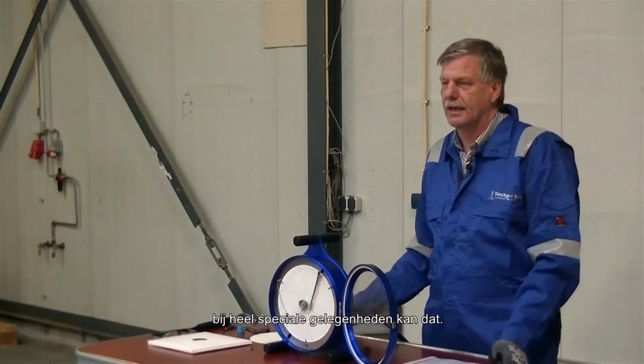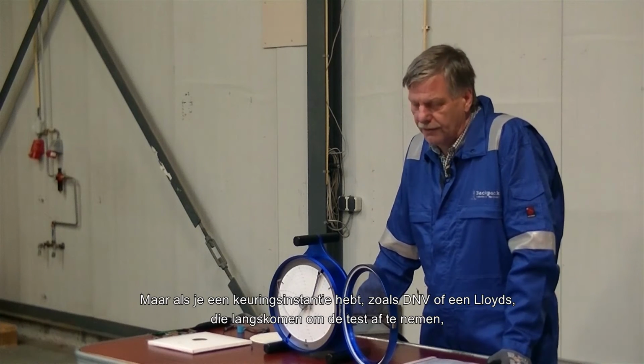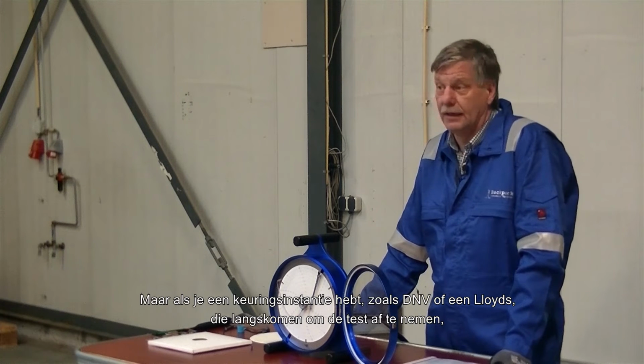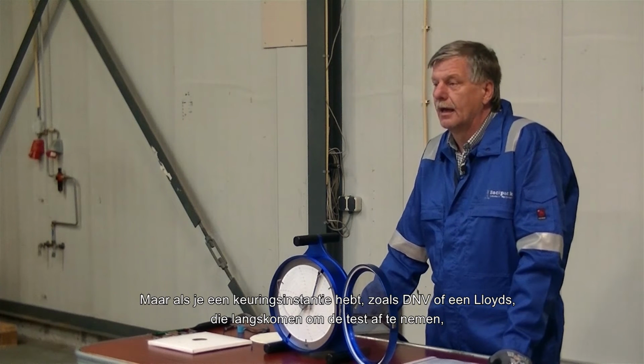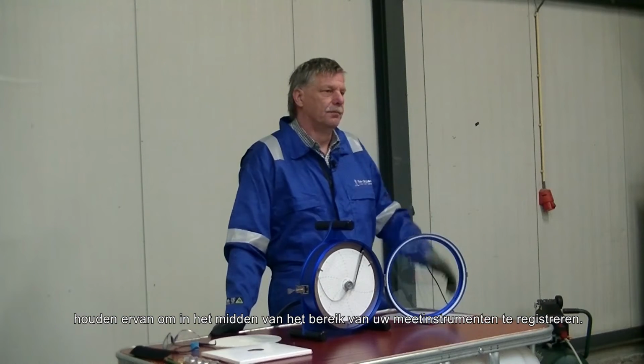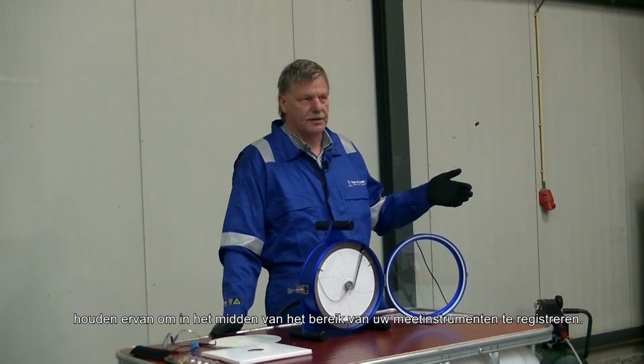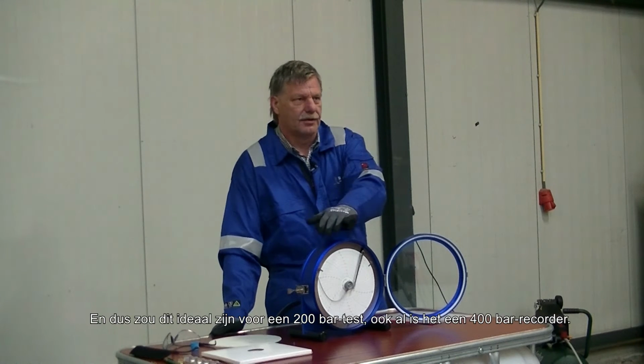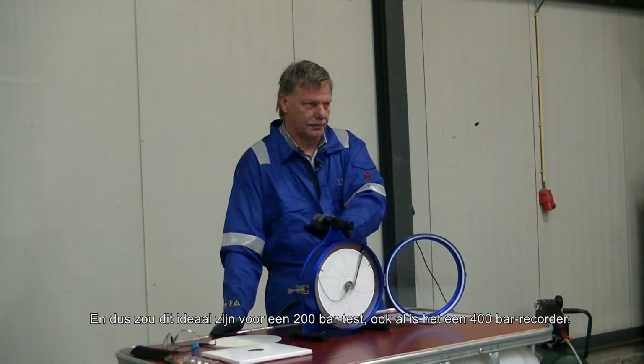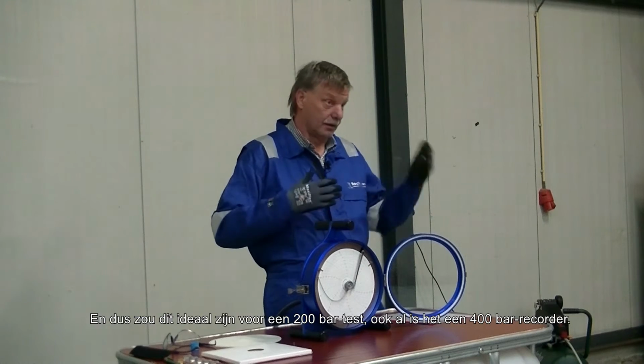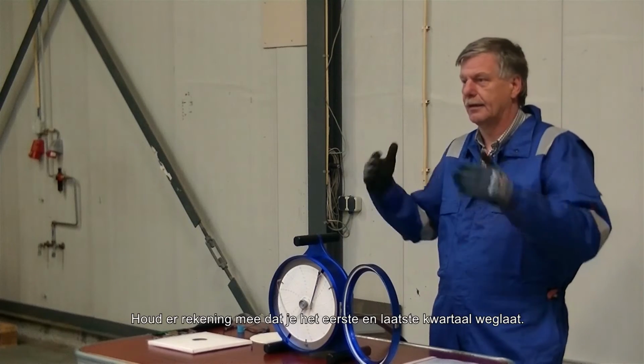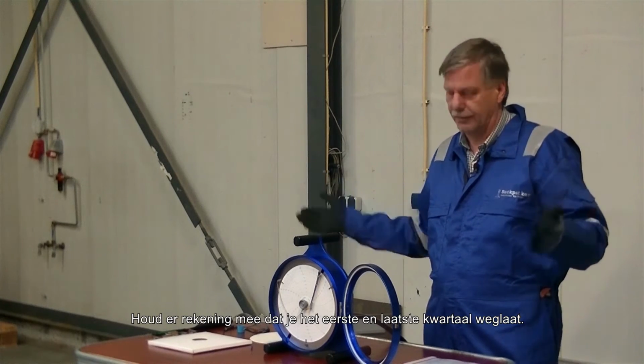In very special occasions you can, but if you have a notified body like DNV or Lloyd's coming in to check up on the work, they like to be in the middle of the range of your measuring instruments, and so this would be ideal for a 200 bar test, even though it's a 400 bar recorder. Bear in mind, leave the first and last quarter out.